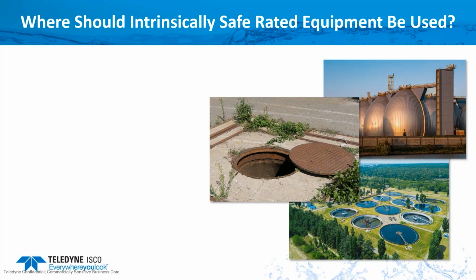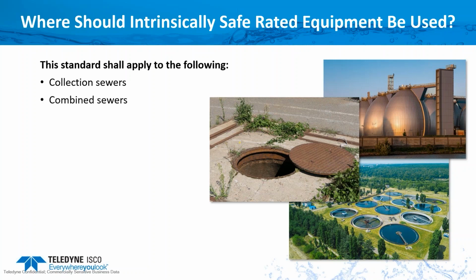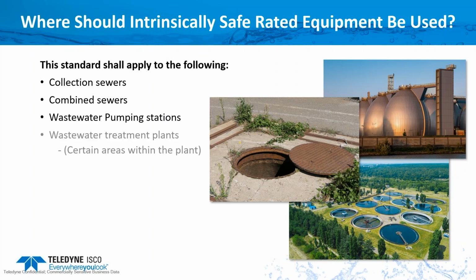So where should intrinsically safe rated equipment be used? Well, the standard applies to the following. Primarily, the collection system is where you're going to see the IS equipment: combined sewers, wastewater pumping stations, and wastewater treatment plants. And this is within certain areas of the treatment plant. Not everywhere in the plant is rated. Most of the time you're going to find that more towards the influent, where you have a lot of the hazardous gases. So why risk it?